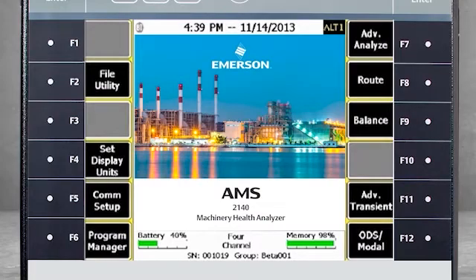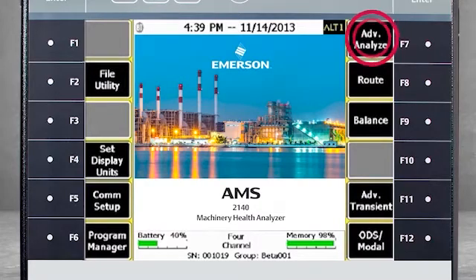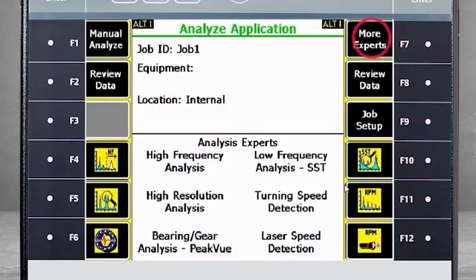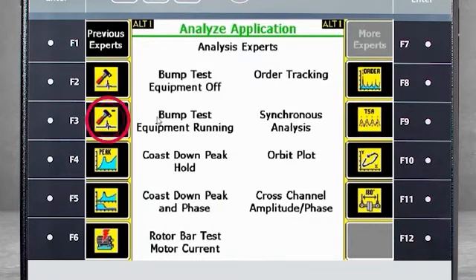Let's look at how to configure negative averaging on the AMS 2140. From the home screen, select F7 Advanced Analyze, then F7 More Experts. Select F3 Bump Test Equipment Running. You'll see some instructions on how to proceed.